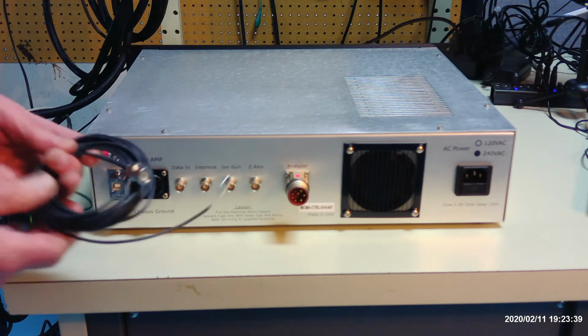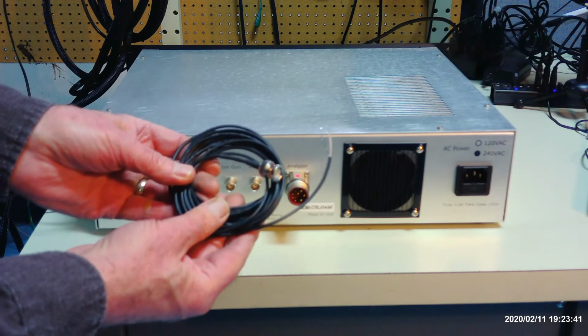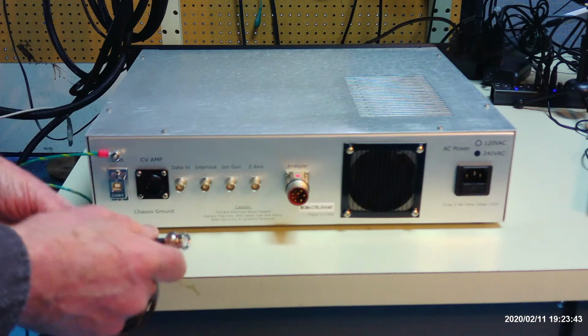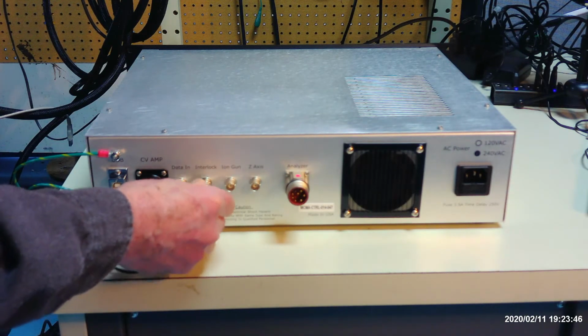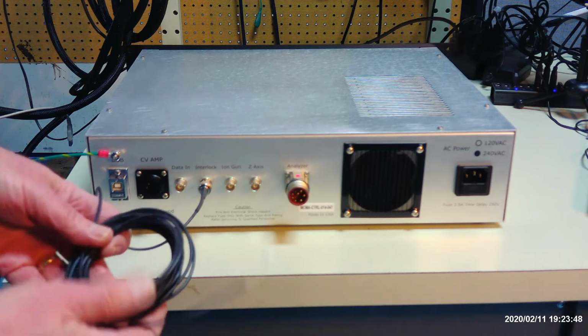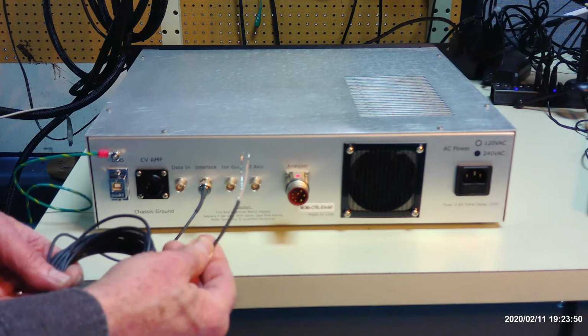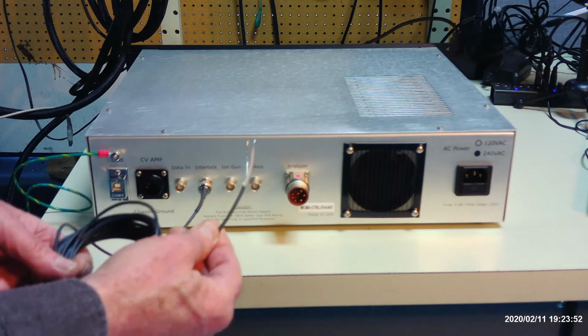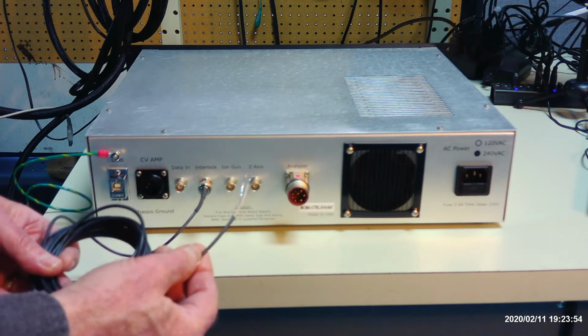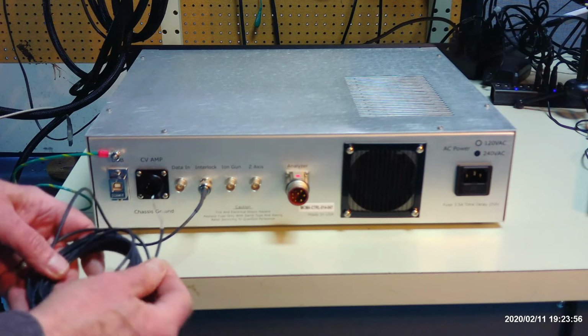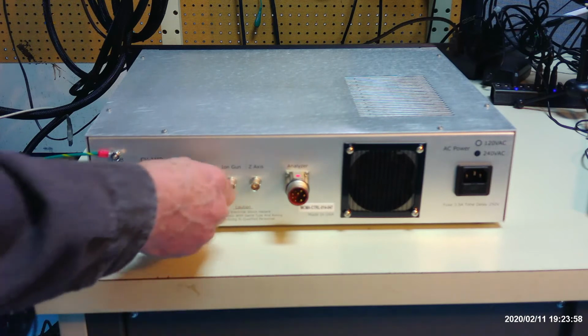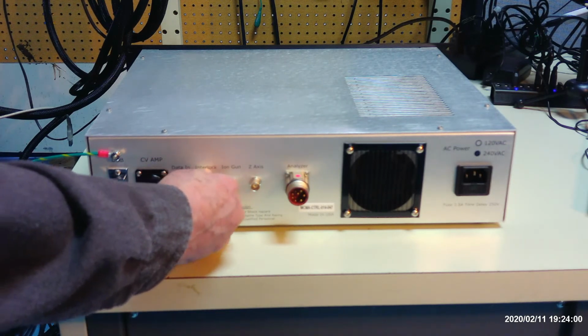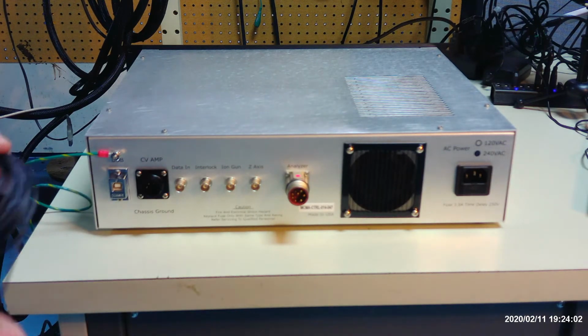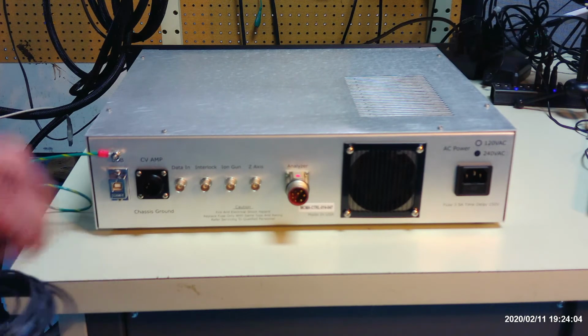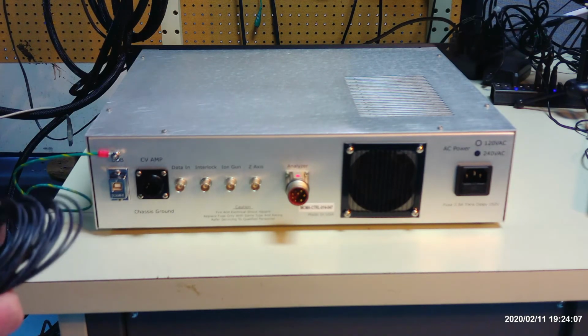Alright, one of the other cables we provide is an interlock cable. This interlock cable would connect to this BNC connector here, the connection that says interlock, and then the other end will connect to your ion gauge set point. This is used so that you can have a set point on your vacuum chamber where, let's say the chamber pressure is above 1 by 10 to the minus 7 torr, you would want to turn off the microCMA controller automatically.